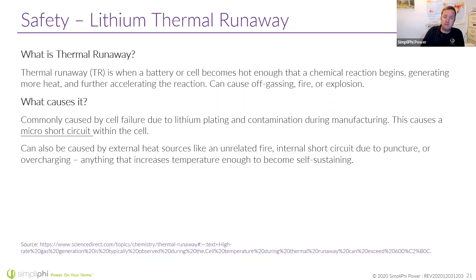Even if you were to force one of these lithium iron phosphate cells into thermal runaway, the temperature at which the material burns is a lot lower. LFP is around 400 degrees centigrade, while NMC cobalt is up at 675. And the temperature you need to reach to initiate that reaction is also higher with lithium iron phosphate - about 200 degrees - whereas it only takes 170 degrees centigrade for cobalt-based chemistries to go into that self-propagation mode.